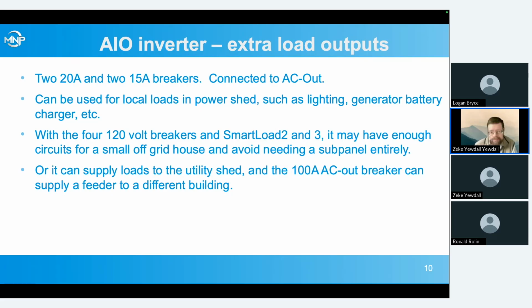I've seen this done on people who are putting in an off-grid house, and they build the shop and the powerhouse first, and eventually they're going to run a feeder over to the main house that can connect into the AC out breaker. But we may be able to feed the small shop just off of a couple of the smart loads. Put a 240 volt well pump on one of the smart loads and some of our 120 volt circuits on those 4 extra breakers. And we may be able to avoid needing a sub panel in that shop completely by just using those extra breakers in the inverter.